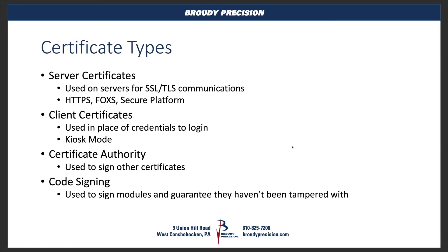A lot of us are familiar with a server certificate, but there are also a handful of other certificates available to us in Niagara that you'll probably come across at some point. The first of these types is a server certificate — the one we've all seen. It comes bundled in a Niagara station as a self-signed certificate known as Tridium, and it's used on servers to allow us to create our SSL and TLS communications — our HTTPS, FoxS, and secure platform connections.